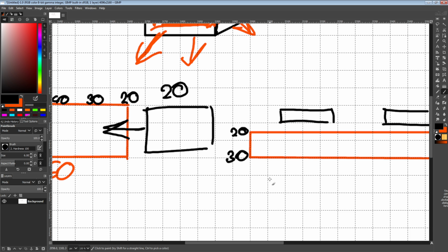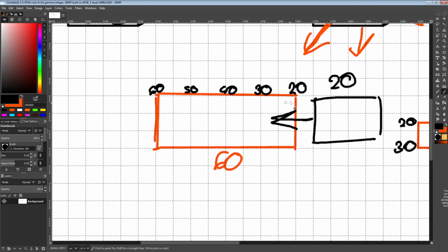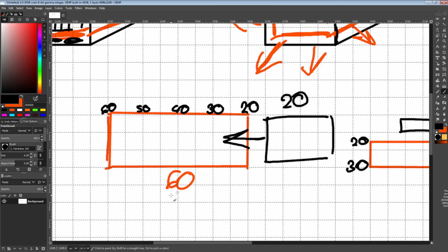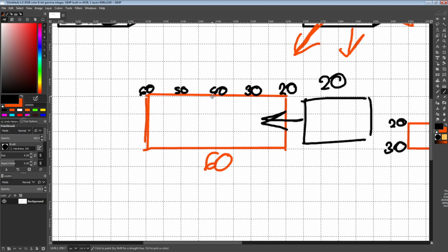Because basically, once the air is at the same temperature as the fin stack, it doesn't do anything. This is really counterintuitive for a lot of people. A lot of people think that if you crank up the water flow through a cooling loop, it makes it worse at cooling, but no, because you end up in the same situation.